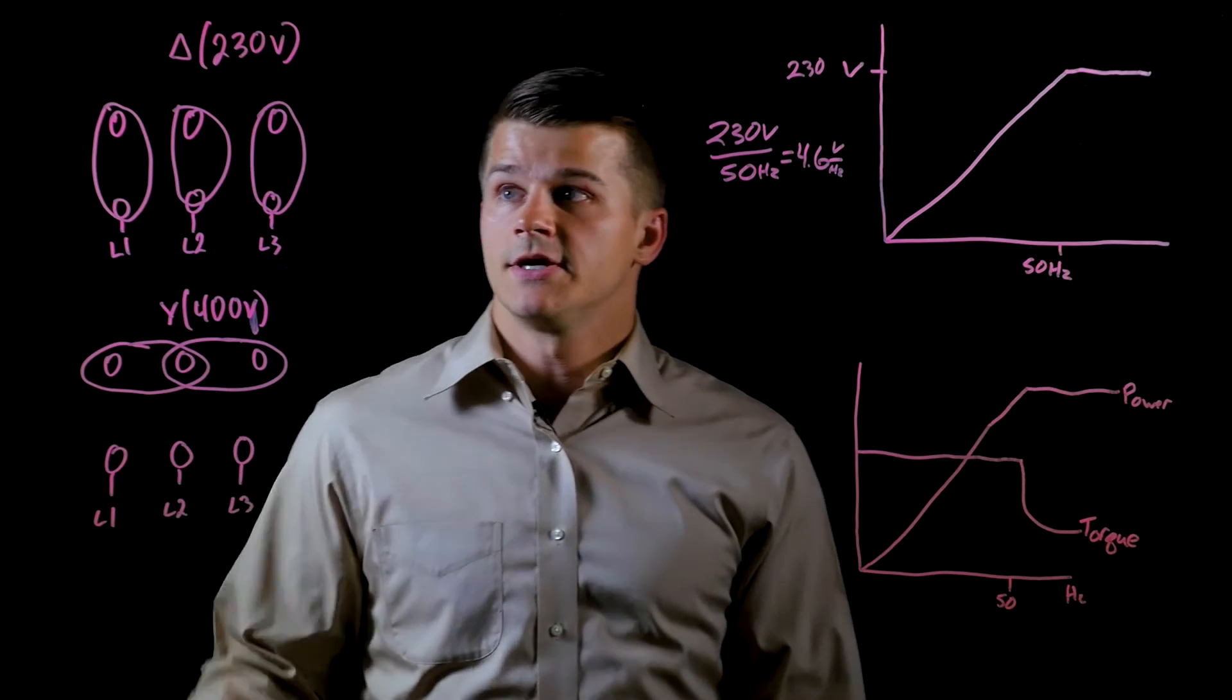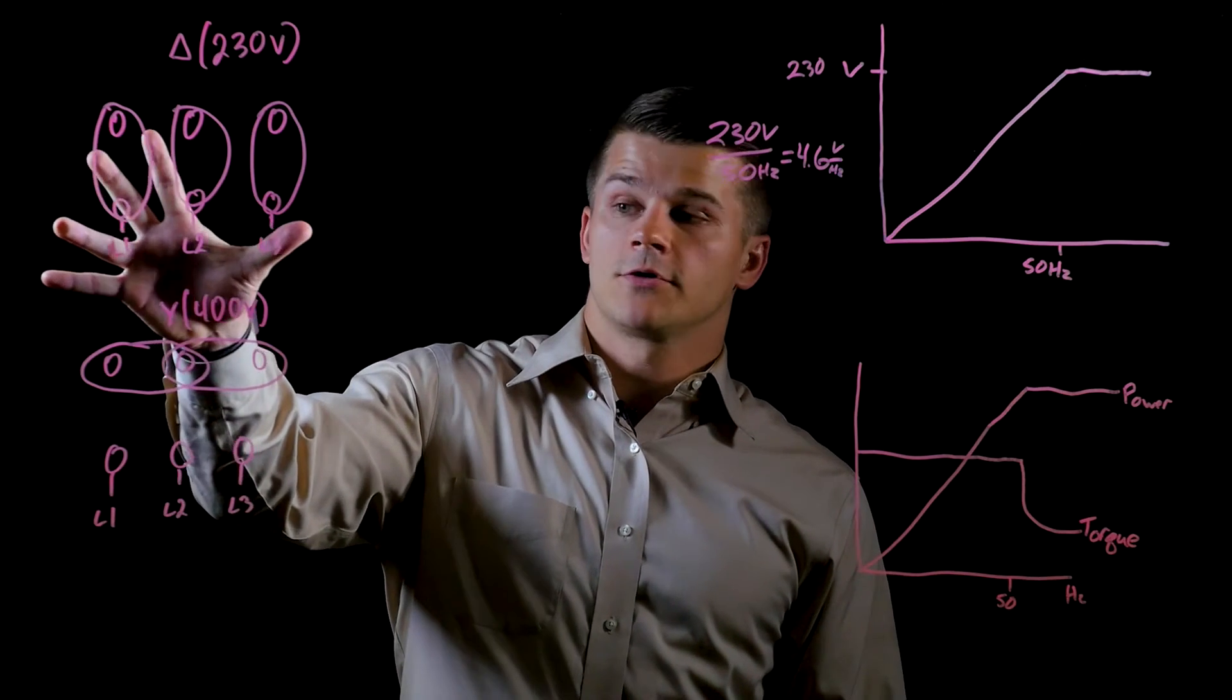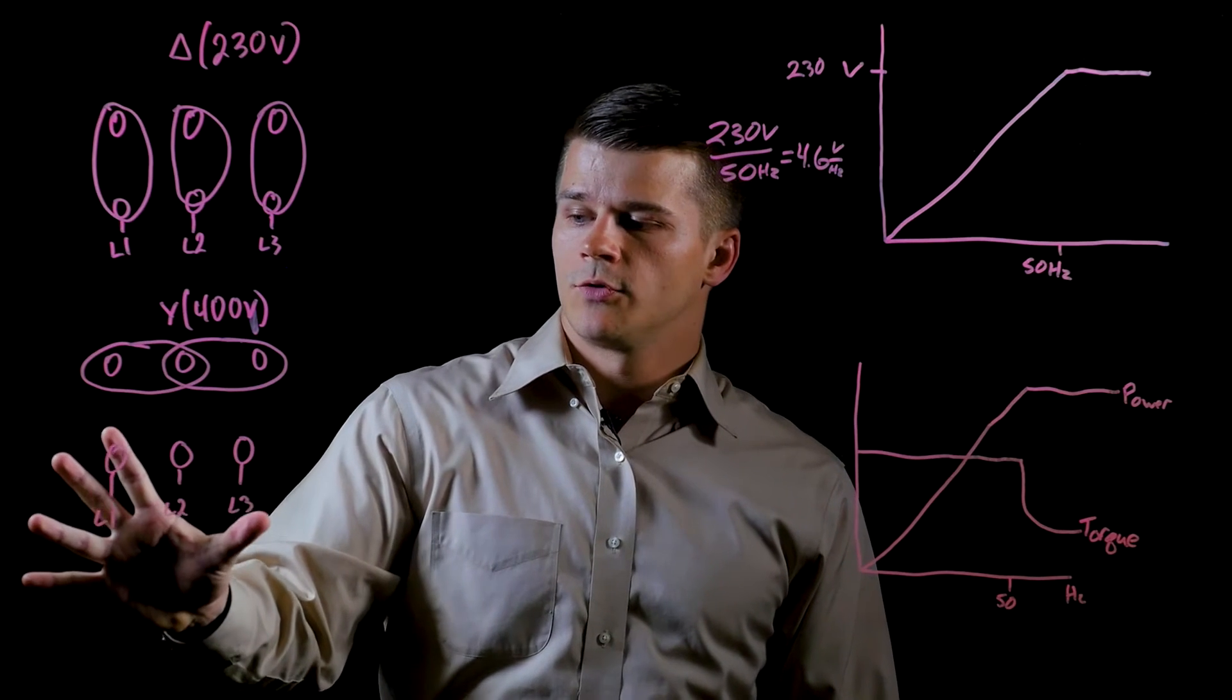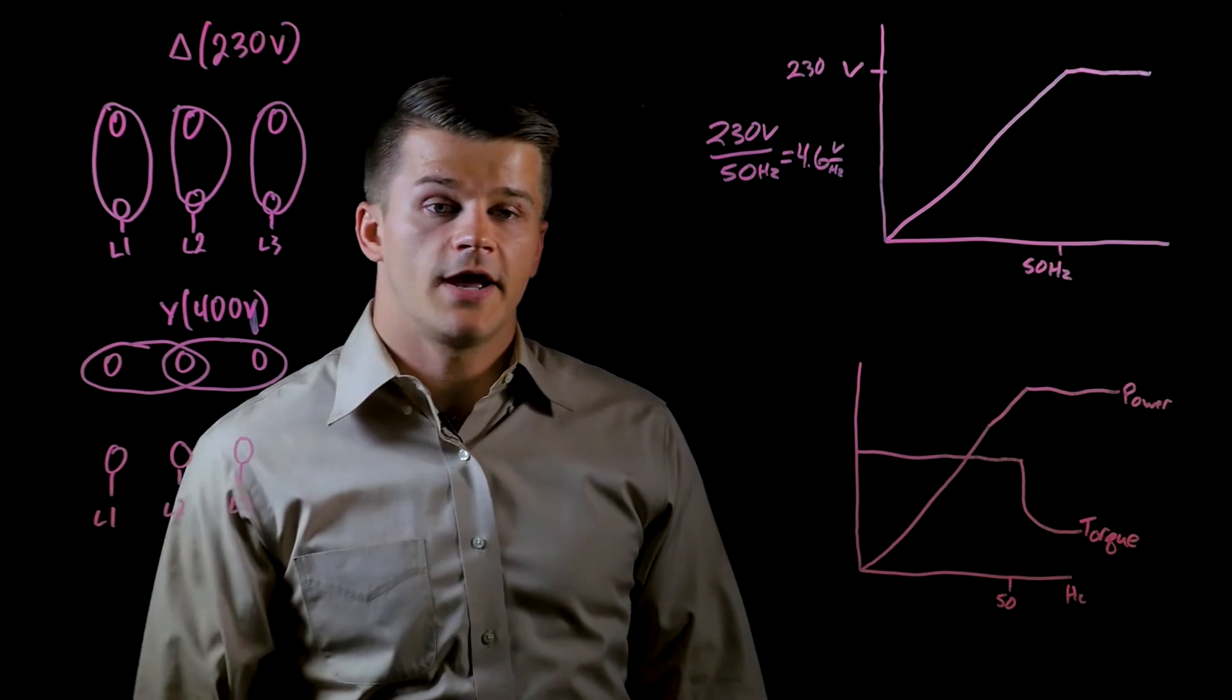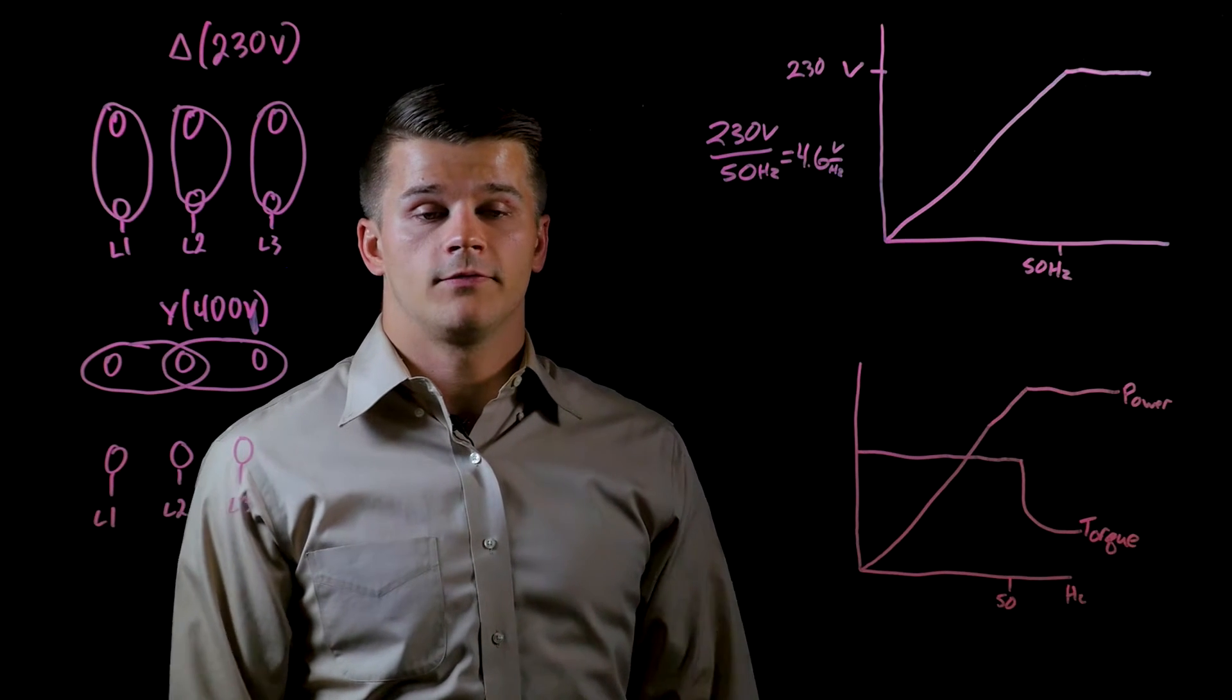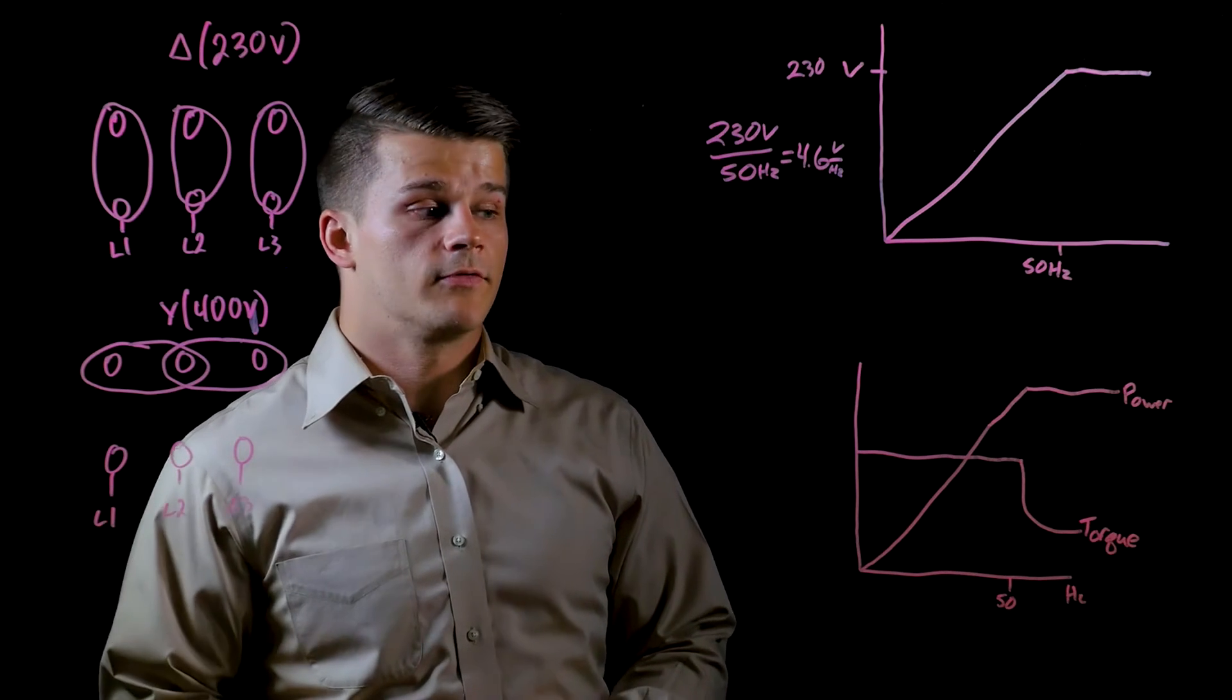What that does is rather than wire it for your 230 volt Delta configuration, you would wire it for the 400 volt Y configuration. The one thing to keep in mind is you would have to have a 400 volt drive in front of it that allows for a 400 volt input to the drive.